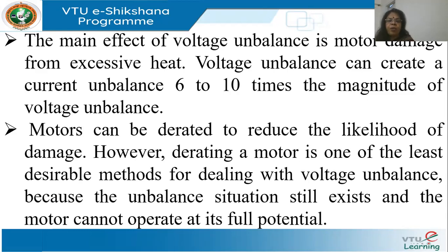So actually the manufacturer will give a derating schedule or a derating curve along with the equipment. It's a data sheet. So for how much percentage of unbalance, how much should you derate the equipment? Predominantly motors and transformers are derated. Okay. So derating is fine if this is a temporary phenomenon.